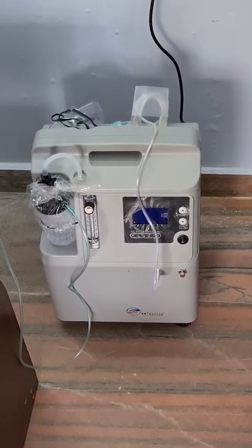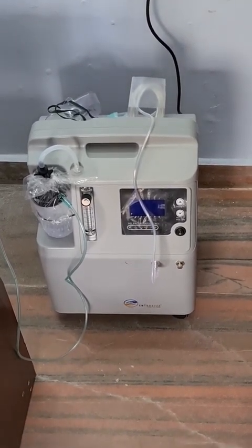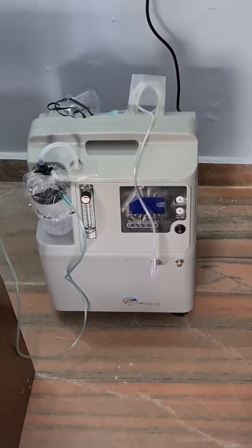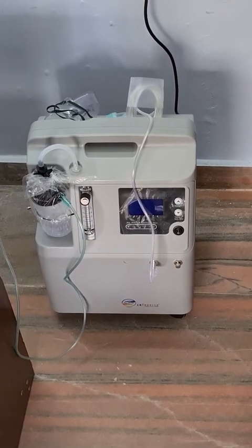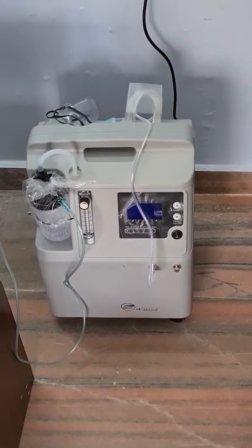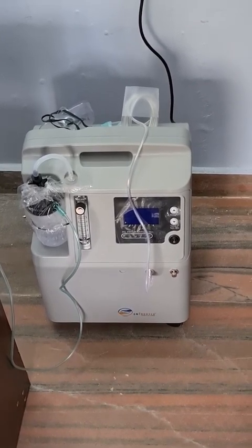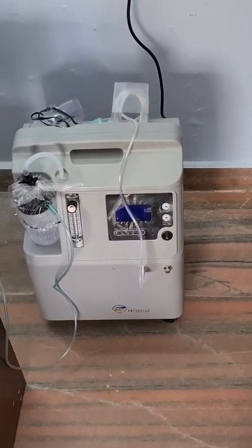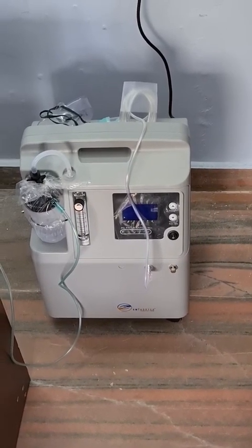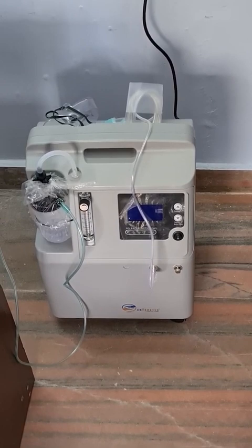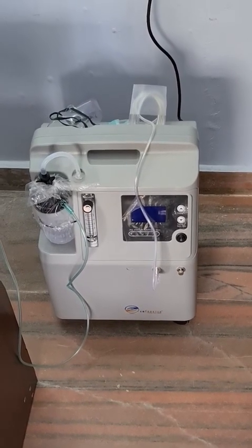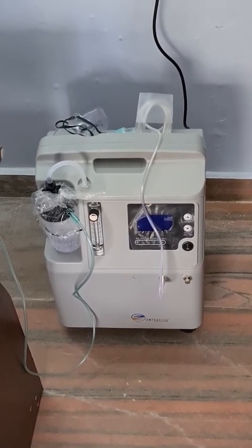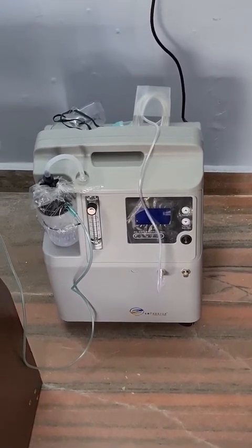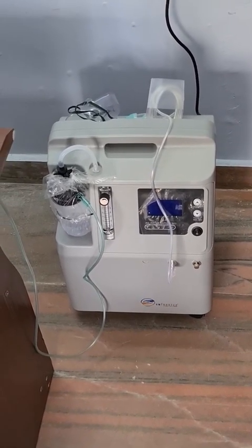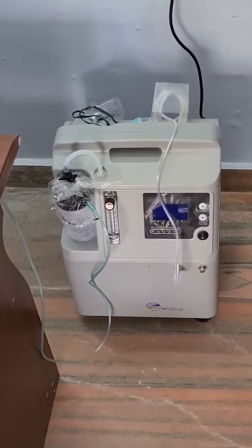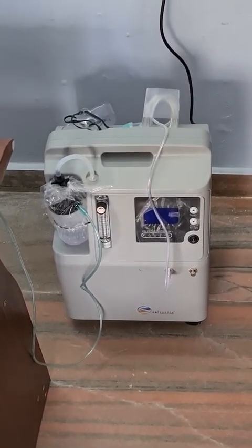Second main thing, placement of the concentrator. Always keep it 1 foot away from the wall, the wheels should preferably be in the lock position, and it has to be on a ground surface. Third main thing, humidification. When you add water to the humidifier, it should be purified RO water, and there should not be any salt in the humidifier bottle. Always make sure not to exceed the maximum mark, otherwise unnecessary water droplets may enter the nasal cannulas. Use the timers only when required. If you want to check the display, press the down button. If you press the upward button, the timer will automatically get switched on.